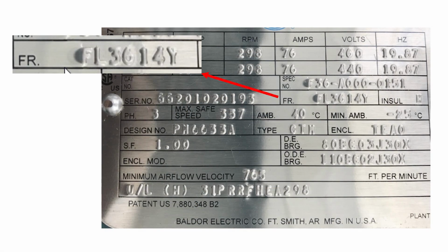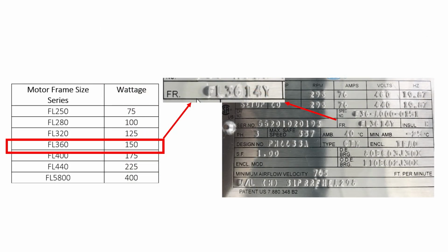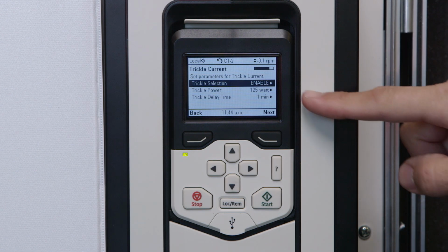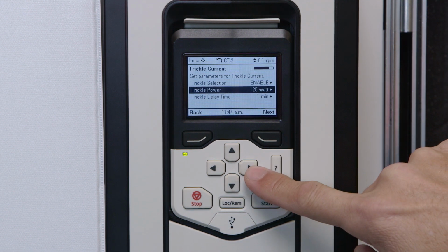To determine your motor frame size, refer to the value found in the section of the nameplate labeled FR. Select the proper wattage based on the motor frame size using the table in the user guide or the chart shown here. The wattage ranges from 75 to 400. For example, if the value in the FR section of the motor nameplate reads FL3203Y, that would correspond to FL320 on the chart, and your corresponding wattage would be 125. Match the first four characters of the frame size on the nameplate to the chart. Change the trickle power to match the frame size of your Enduradrive motor and then press Save.